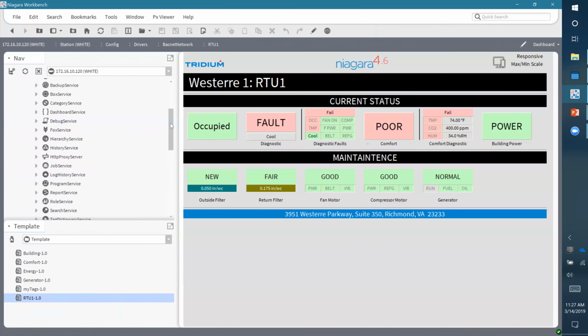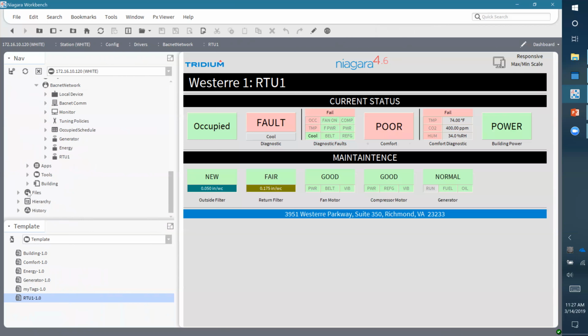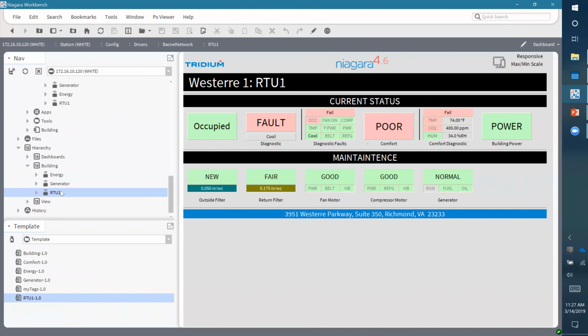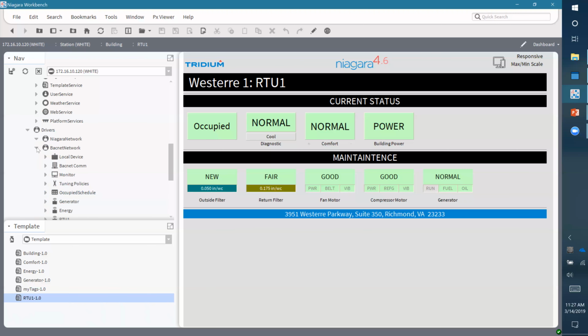And then we'll take a look at, here's my hierarchy. Come down here to hierarchy, and we have buildings, and then you'll see my rooftop unit. Boom, we're ready to go. So you notice all my analytics are now going green because I refreshed the cache. So this device is up and running using one of those device templates for that rooftop unit. Okay, if I go down to let's say, a location and they have 4 rooftop units and only one is connected, I can still go in and add this template to the existing JACE and then match the devices later.